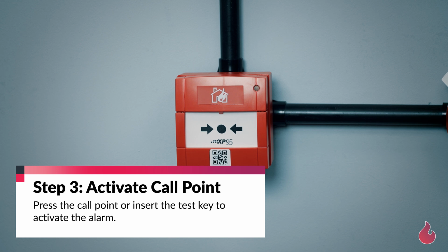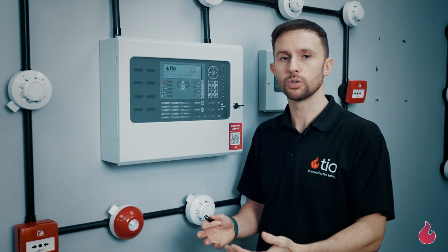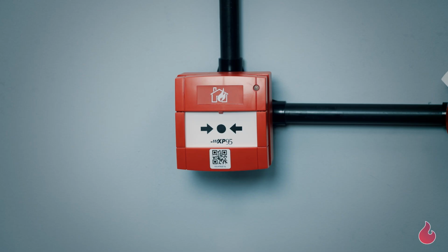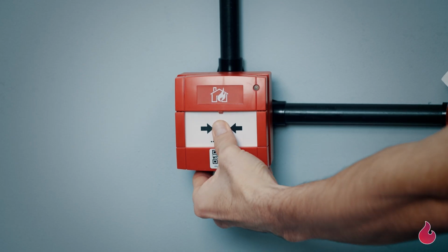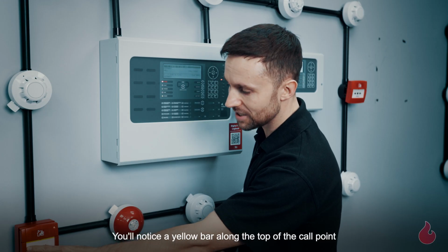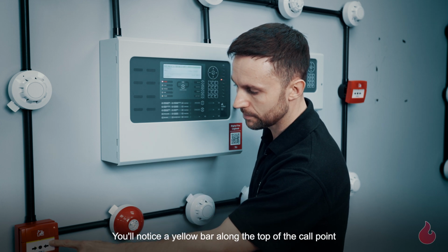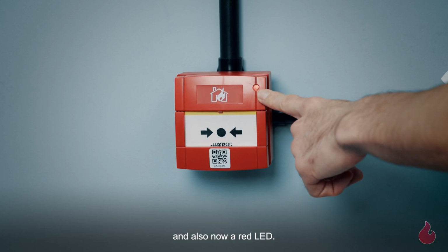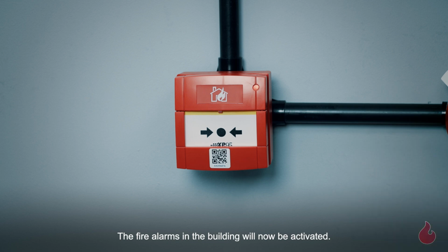Depending on the model of the call point, this particular model is a resettable element. So all I'm going to do is walk up to the call point and press it with my thumb, just like this. You'll notice a yellow bar along the top of the call point and also now a red LED. The fire alarms in the building will now be activated.